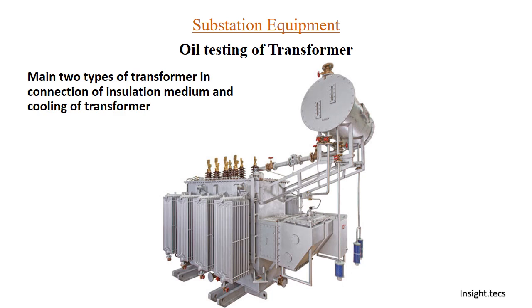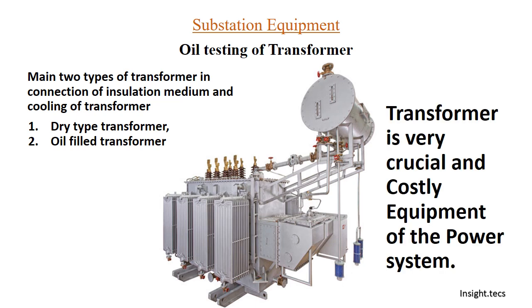Based on the type of insulation mediums and cooling, transformers are categorized as dry type and oil-cooled transformers. We are going to discuss about oil-cooled transformers today. Transformer is a very crucial and most costly equipment of the entire switchyard, hence it is very important to perform routine tests on the transformer — to take oil samples every year and get different kinds of testing done to diagnose any fault prevailing inside the transformer.